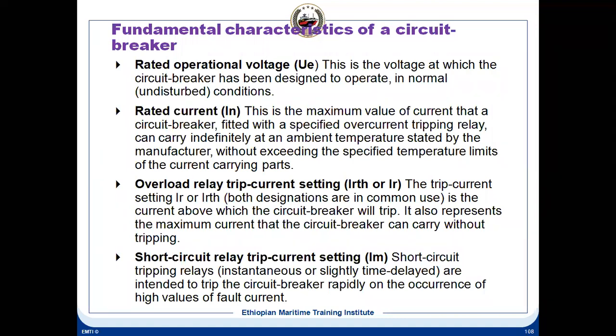Rated current is written In. This is the maximum value of current that a circuit breaker fitted with a specified overcurrent tripping relay can carry indefinitely at an ambient temperature stated by the manufacturer. Overload relay trip current, you can see Ir or Irth. This is called the trip current setting, the current above which the circuit breaker will trip. It also represents the maximum current that the circuit breaker can carry without tripping.